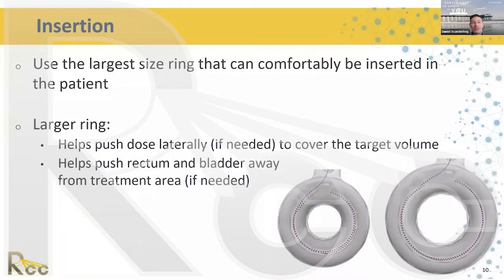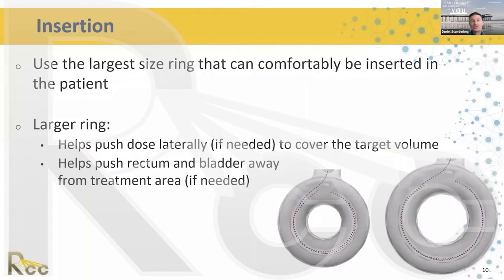Some clinics have in-room imaging available. Transrectal or transabdominal ultrasound during placement can help visualize correct applicator positioning and prevent perforation. Fluoroscopy can also be used during insertion to help visualize the implant. Some implant in a room with CT or another imaging modality available during the procedure. It's important to check with the physician on their training, ensure all equipment is working, and that all staff are properly trained in its use.